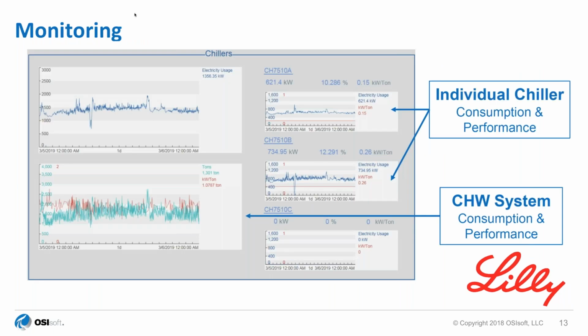They had noticed that when they looked at the data in the control system, they were seeing performance problems. But in a control system, a couple of things have to occur. One, are you licensed for data beyond 90 days? Are you licensed to have raw data versus PDF or file? Have you turned on trending per tag, and every tag that you need, so that you have a history? All of these things they started to run into.